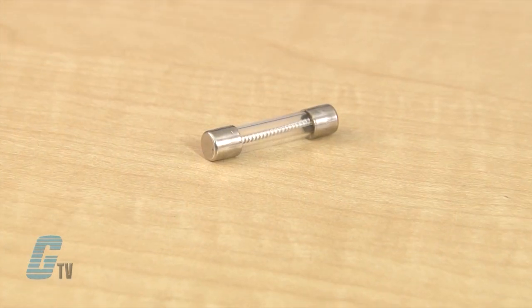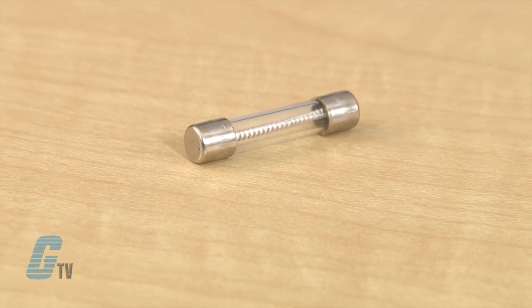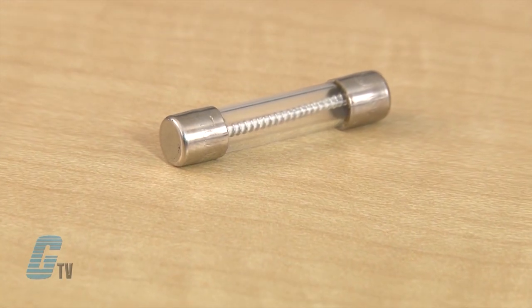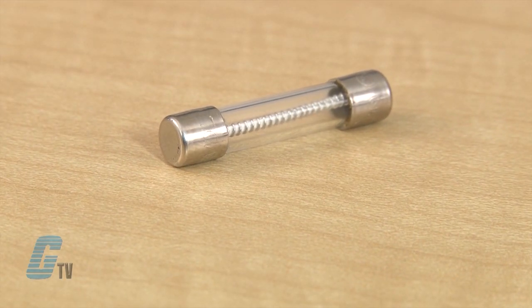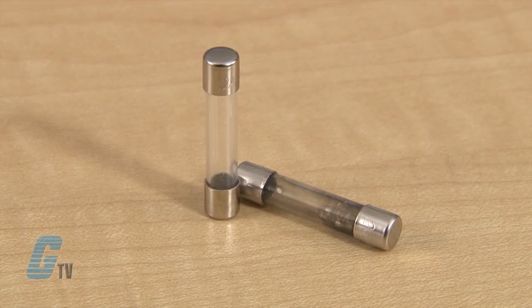Fuses tend to be less expensive than circuit breakers and are also considered safer due to their current interruption capacity rating. The overall footprint of the fuse or fuse block will also be somewhat smaller than that of a comparably rated circuit breaker in most cases. One disadvantage of fuses is that they need to be replaced once they are blown.